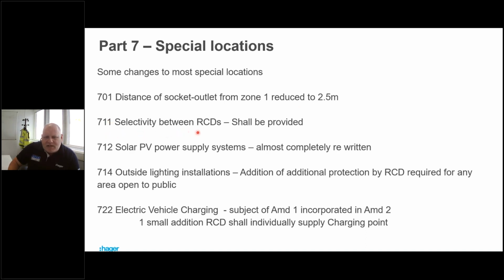711. Okay, selectivity between RCDs. Now, it used to say selectivity between RCDs where necessary. It now says shall be provided. Okay, solar PV. Okay, 712 has been completely rewritten. There's a lot of work gone into that one. 714, outside lighting installations. The addition of additional protection by RCD required for any area open to the public. Okay, so public car park, okay, with outside lighting, we now have to have additional protection via 30 milliamp RCD.